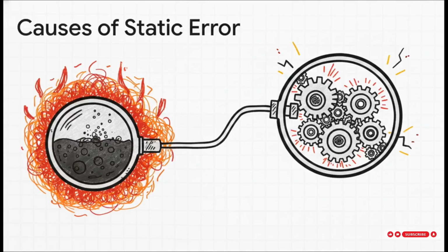Now, a standard pressure spring thermometer uses the expansion of a liquid or gas inside a metal bulb to physically move linkages and point to a temperature. But, well, physical parts have serious physical limitations in those extreme environments. After they've been installed for a while, these thermometers suffer from calibration drift. Even worse, at those massive temperatures, the pure filling media inside the bulb, stuff like mercury or nitrogen, can actually become contaminated or, crazy enough, literally decompose.